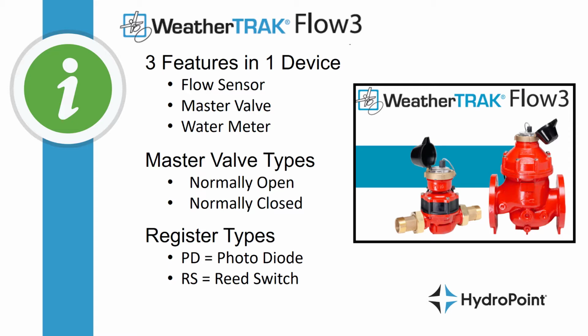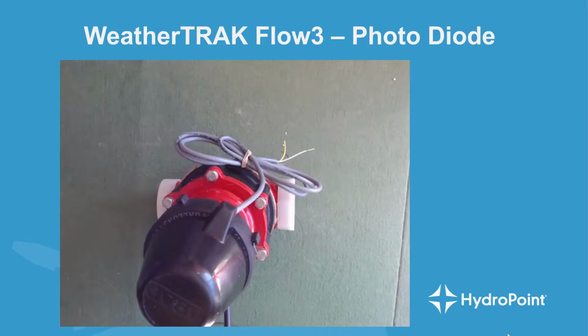The Flow 3 is available with either a normally open or normally closed master valve, as well as an option of the type of register you want to use, either a photodiode or a reed switch. Today's training will focus on the installation of a photodiode Flow 3 when the sensor is directly wired to the controller instead of on a two-wire path. Let's begin with a quick examination of the Flow 3 hardware.